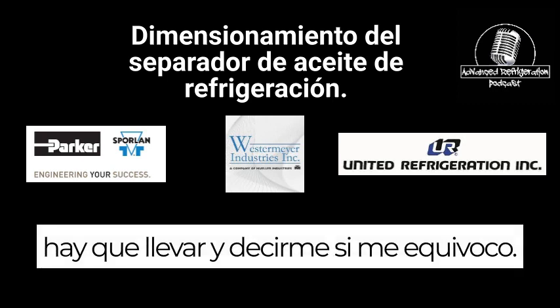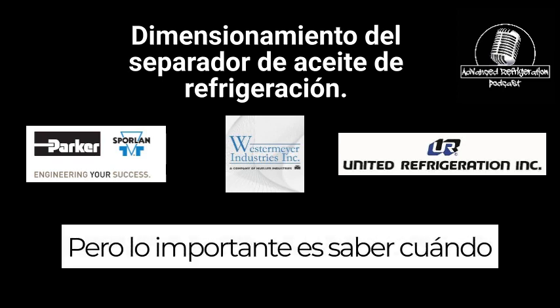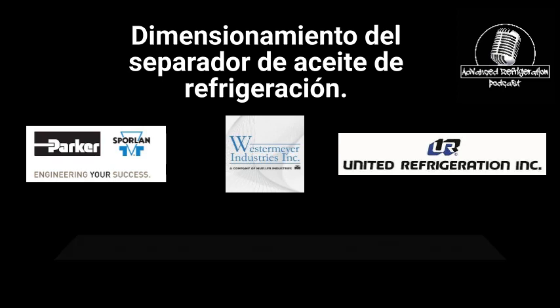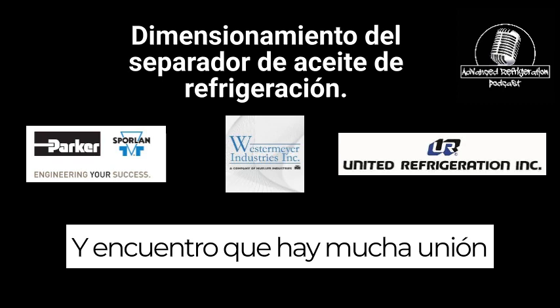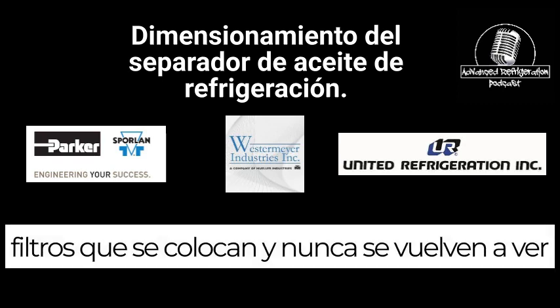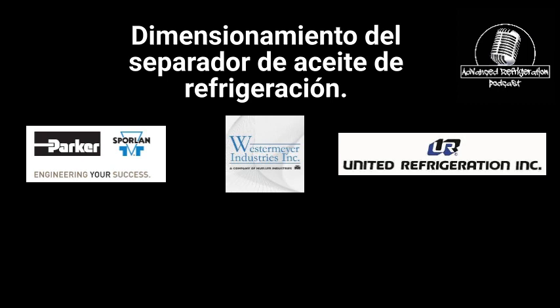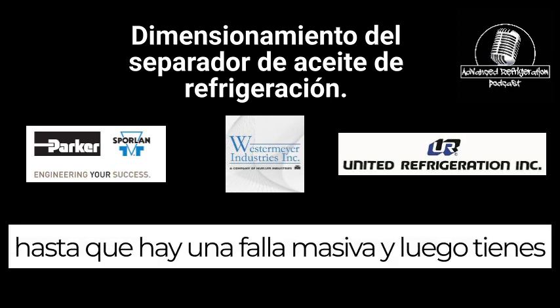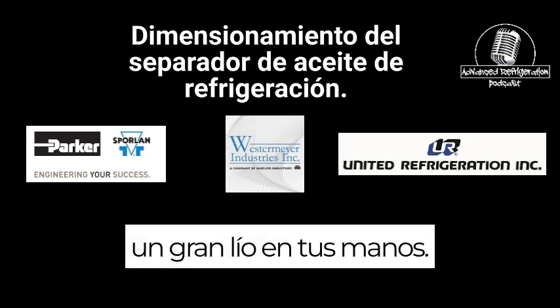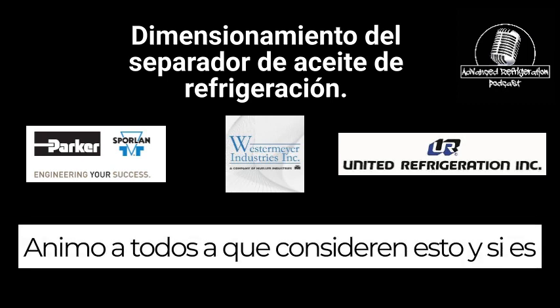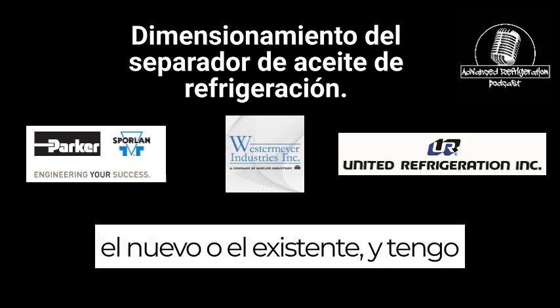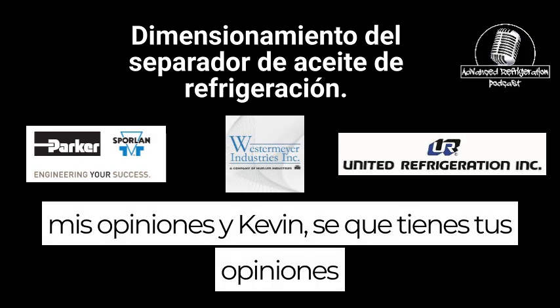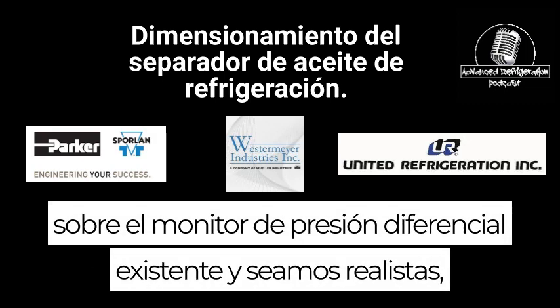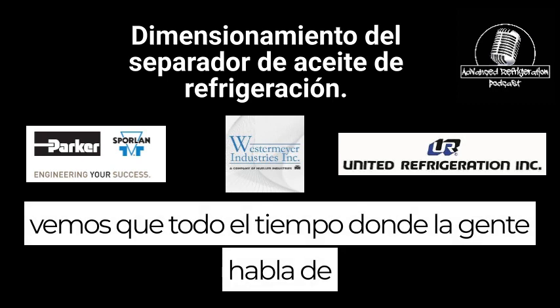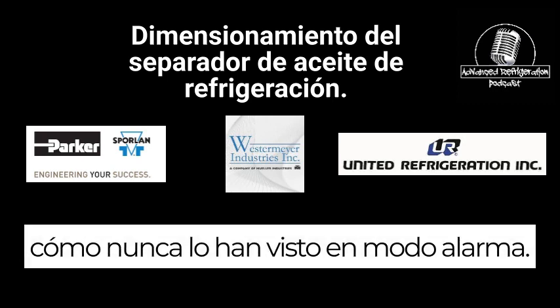And you can tell me if I'm wrong, but the big thing is knowing when that filter needs to be changed. I find that a lot of coalescing filters are dropped in and never seen again until there's a massive failure, and then you've got a really big mess on your hands. So I just encourage everybody to consider this, whether it's the new monitor or the existing one. I have my opinions, and Kevin, I know you have your opinions about the existing differential pressure monitor. And let's face it, we see all the time that people say they've never actually seen it in alarm mode.